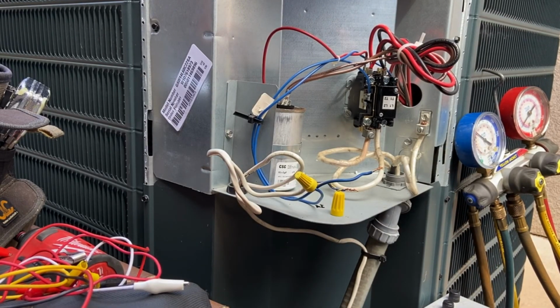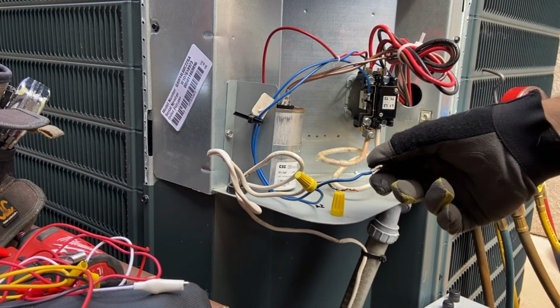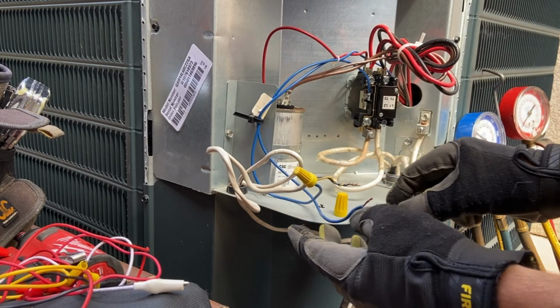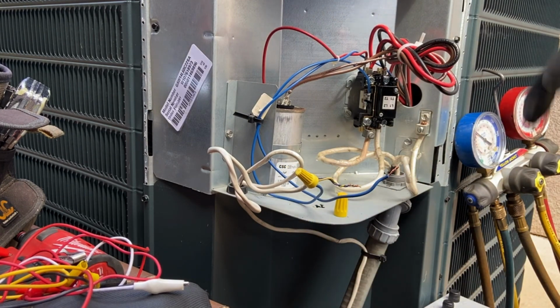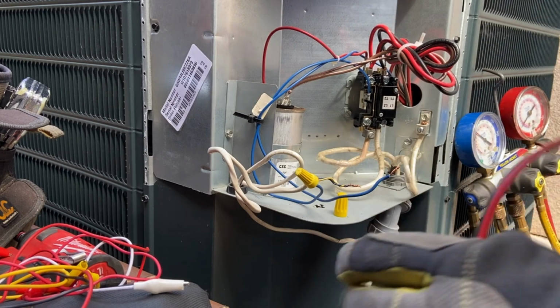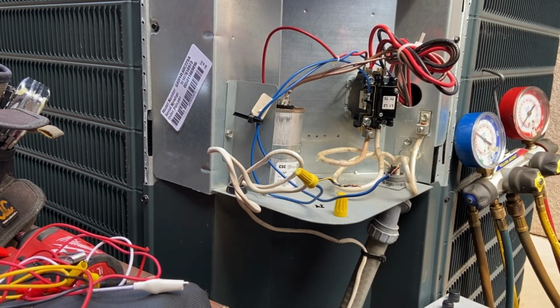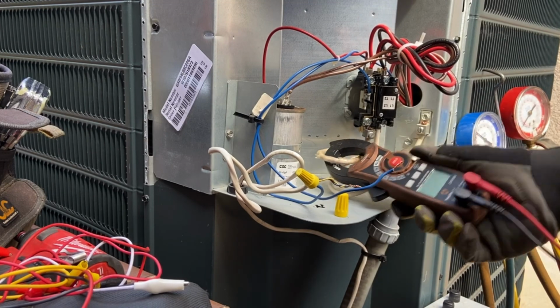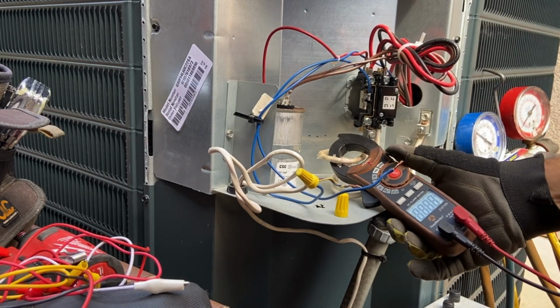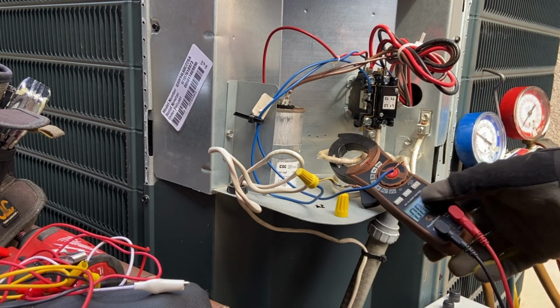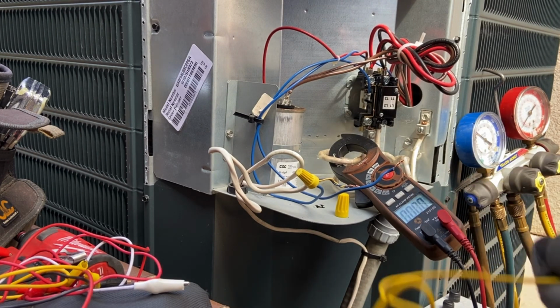All right, this is how I like to do start and test on a piece of equipment. Instead of going up to the thermostat, starting the unit, and coming back down here, I've lost the first 30 seconds to a minute of the unit operation, and sometimes that's critical when I'm trying to diagnose a piece of equipment. So I'll come down and disconnect the control wiring down here, go turn on the thermostat, and come back down here, so that I am in full control when I want to operate this unit. I'm going to put my meter on. I'm going to set it to the 40 amp scale so I can watch the amperage draw when this unit starts. I've got my jumper.